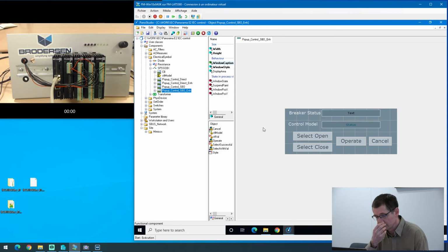So this is the support for control models by Panorama. But Panorama also supports other services from IEC 61850. We support, for instance, the time quality, which means that you not only receive from the IEC a quality on the value of the information, but you also receive information on the time quality. It gives you the date precision. Is it millisecond or is it microsecond? And if it's microsecond, of course, Panorama keeps the microsecond resolution of your timestamp in the alarms and in the archives.